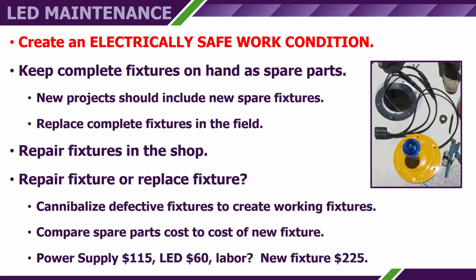You want to keep complete fixtures on hand as spare parts. New projects should include new spare fixtures. And the FAA will fund spare parts for these fixtures in the original project. There are some means to do that in their funding criteria. We recommend that you replace the complete fixture in the field. It's faster. You simply go out there, unbolt it, replace the fixture and transformer, and take care of any repairs or troubleshooting in the shop.